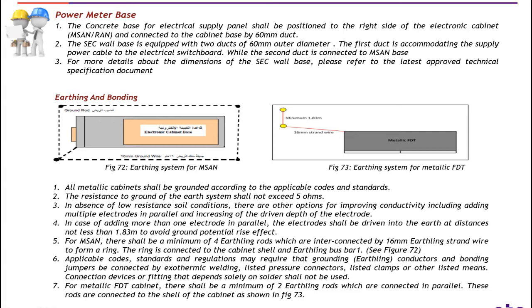Earthing and bonding — there are two different methods of earthing system: one for MSAN and one for metallic FDT. All metallic cabinets shall be grounded according to the applicable codes and standards. Resistance to the ground of the earth system shall not exceed 5 ohms. In absence of low resistance soil conditions, there are other options for improving conductivity, including adding multiple electrodes in parallel and increasing the driven depth of the electrodes.